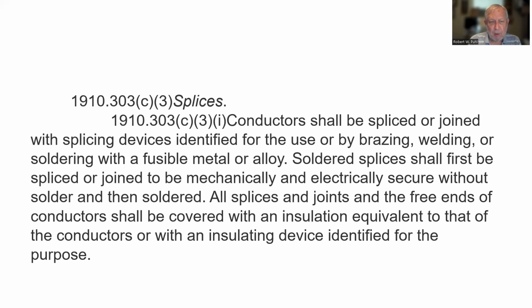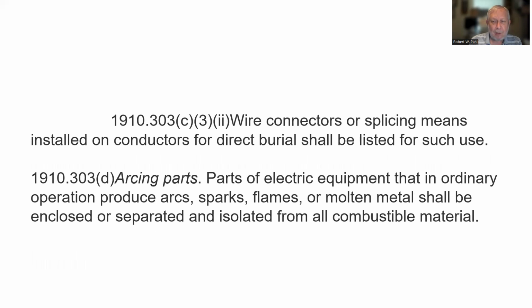Splices: conductors shall be spliced or joined with splicing devices identified for the use, or by brazing, welding, or soldering with a fusible metal or alloy. Soldered splices shall first be spliced or joined to be mechanically and electrically secure without solder, and then soldered. All splices and joints and the free ends of conductors shall be covered with an insulation equivalent to that of the conductors or with an insulating device identified for the purpose. Wire connectors or splicing means installed on conductors for direct burial shall be listed for such use. If they put something in the ground, it better be made for that.